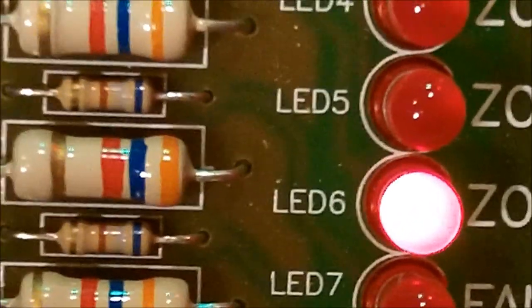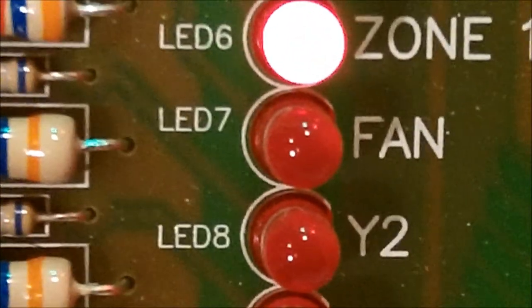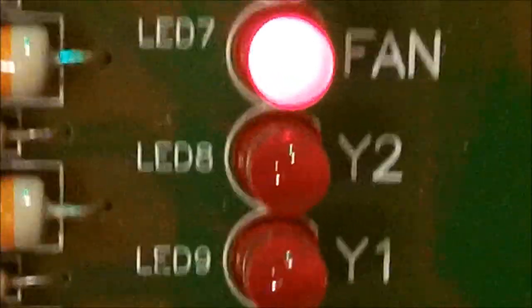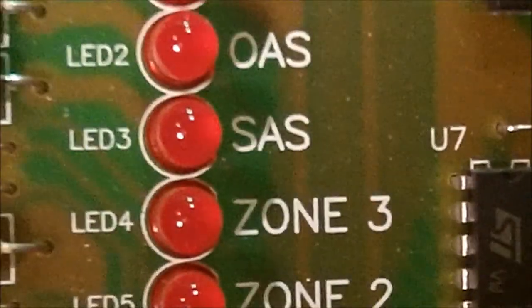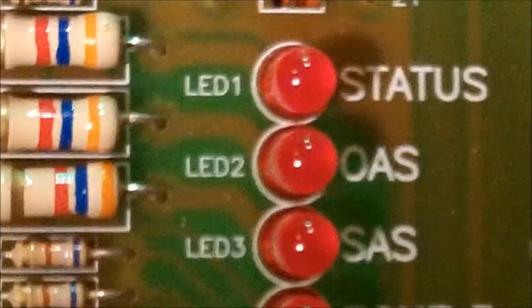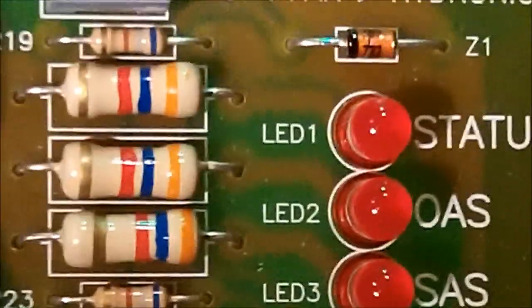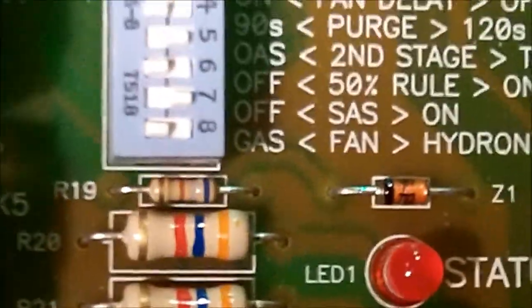It's not, so let me run this temperature down. Alright, so the furnace is going to go off. Alright, so the fan came on because I've got the fan set in the on position. You have your Y1, your W1 there at the bottom, W2 in emergency, and that's it as far as the zone board goes. So let's talk about the operation, about what happens when what calls on the thermostat and the zone dampers, and we'll go into operation of the air conditioner.